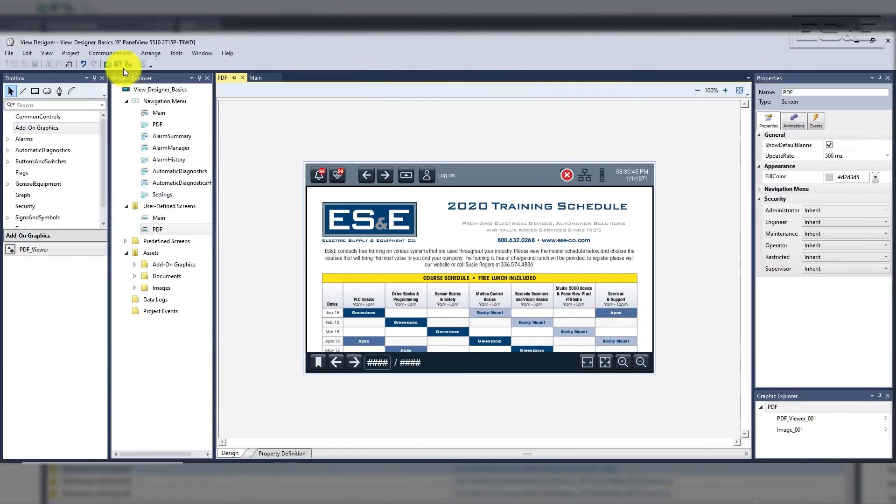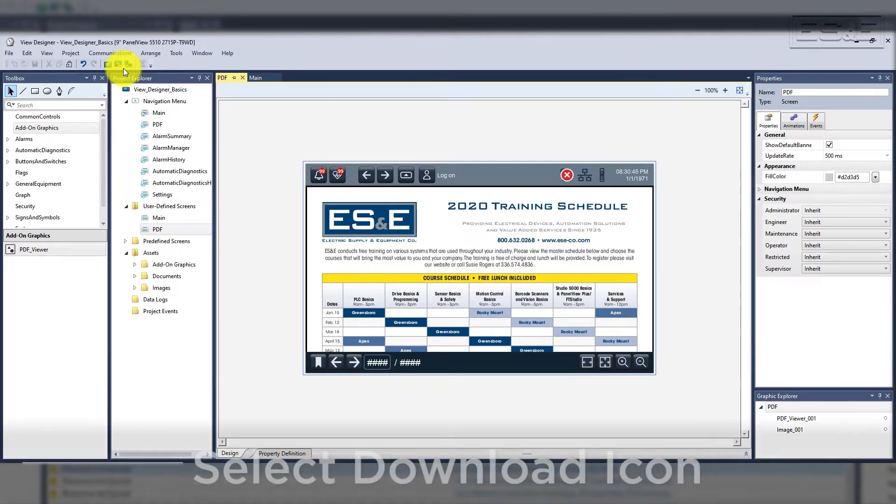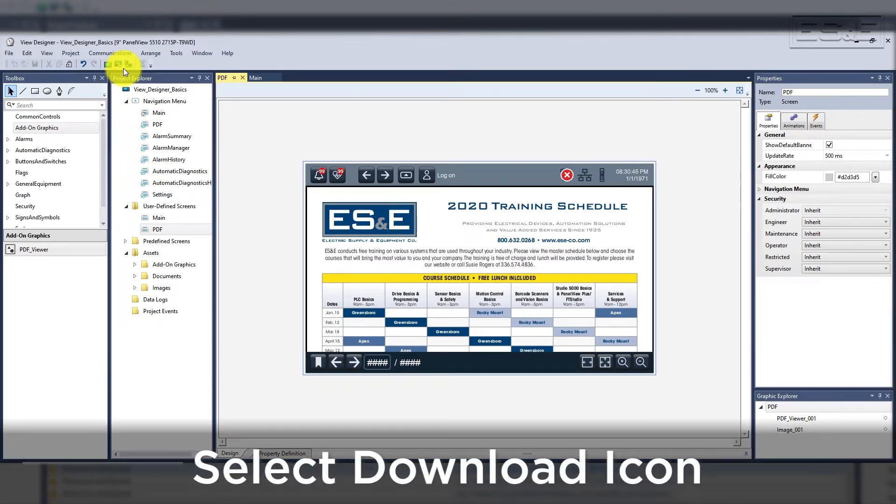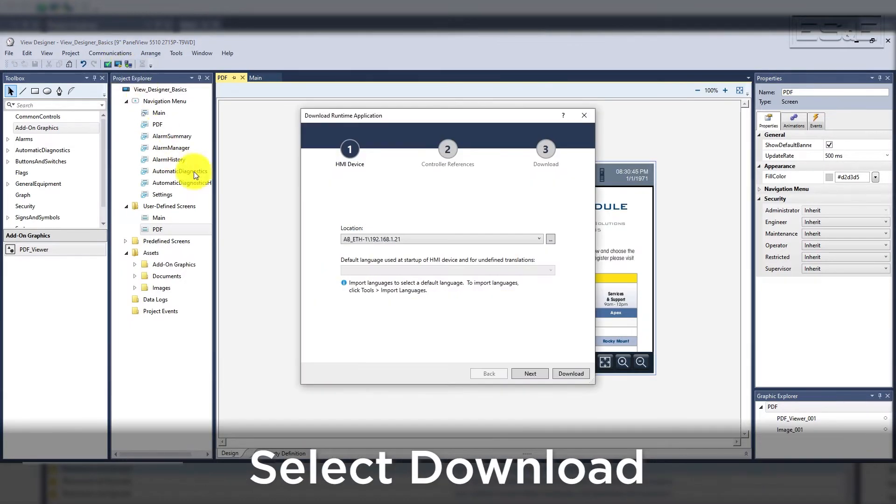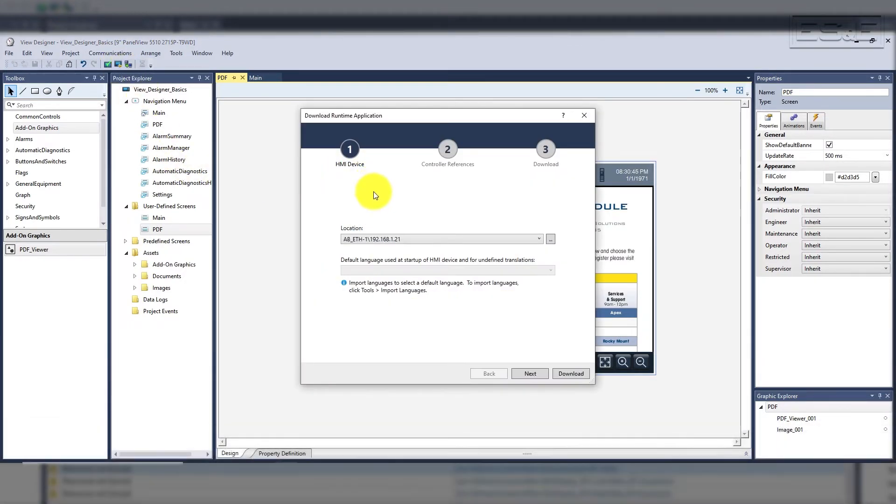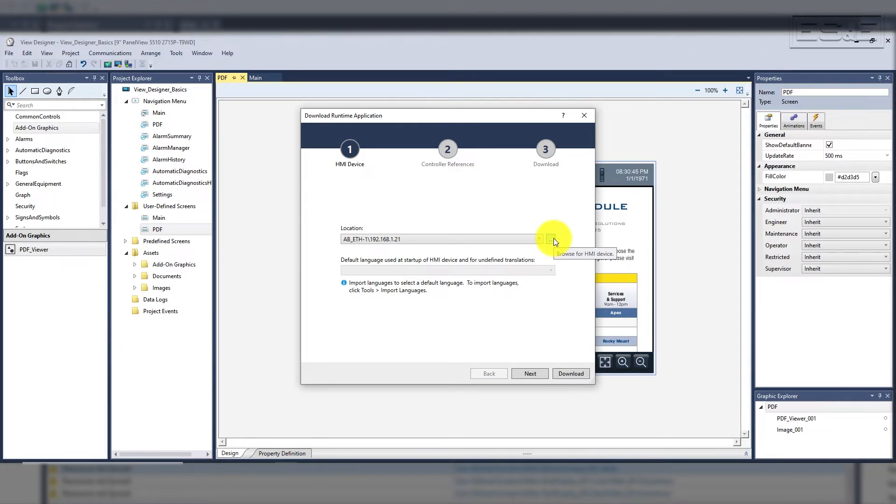To download in Studio 5000 View Designer, you need to open the project and you can select the download icon in the toolbar or select the communications, then download. When you select download, it will launch a new window with the path you created in the project settings under the HMI settings.